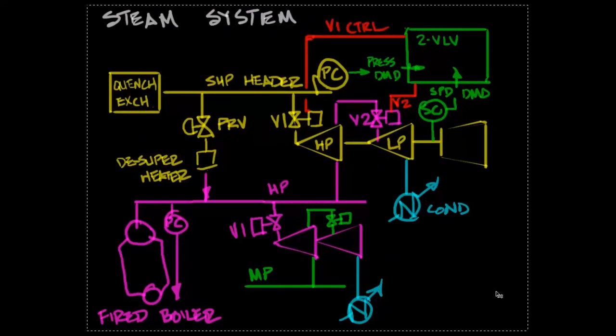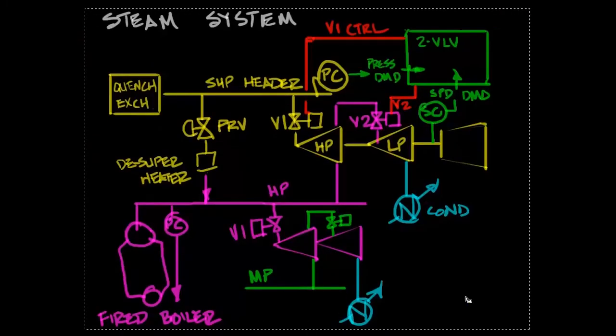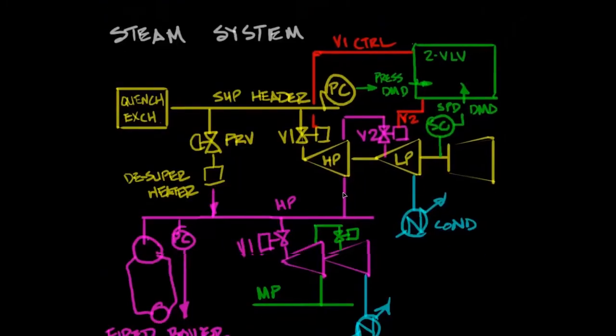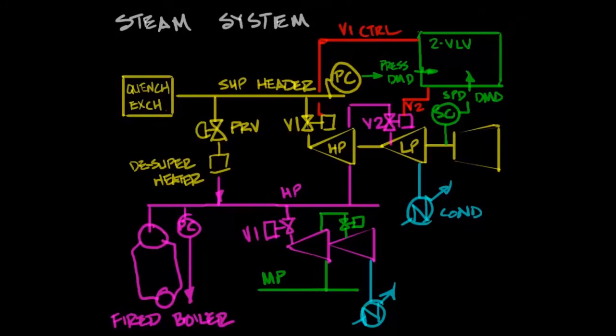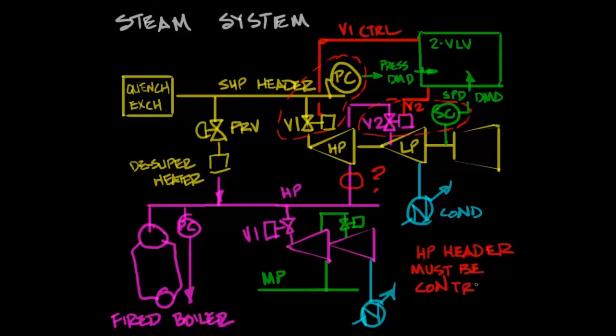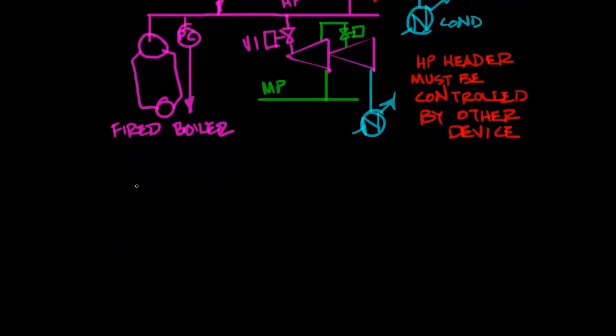Let's look at that steam system again one more time. What we're saying then is the pressure controller that's managing the SHP header pressure is going to manage V1 and the speed controller is going to manage V2. So what does that leave for the header pressure, the extraction pressure or any control of that.